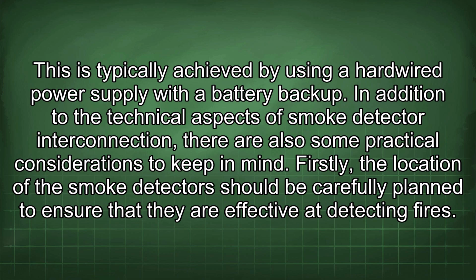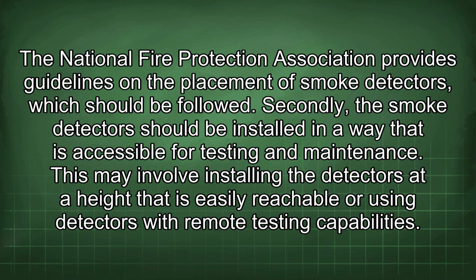In addition to the technical aspects of smoke detector interconnection, there are also some practical considerations to keep in mind. Firstly, the location of the smoke detectors should be carefully planned to ensure that they are effective at detecting fires. The National Fire Protection Association provides guidelines on the placement of smoke detectors, which should be followed. Secondly, the smoke detector should be installed in a way that is accessible for testing and maintenance. This may involve installing the detectors at a height that is easily reachable or using detectors with remote testing capabilities.